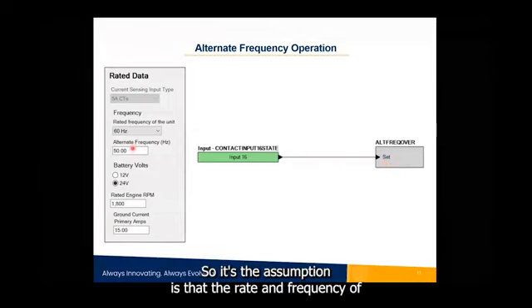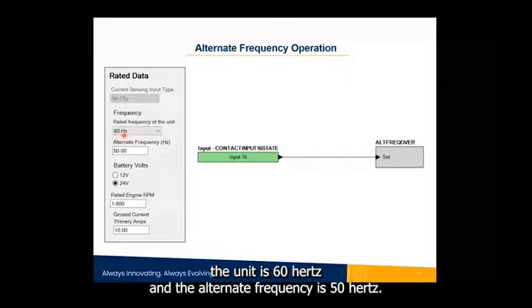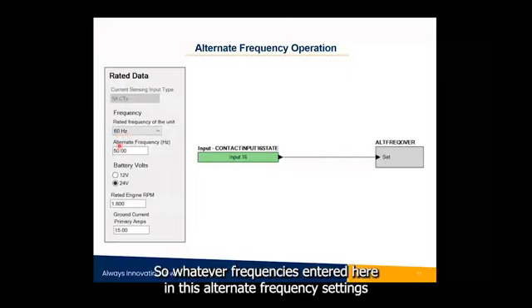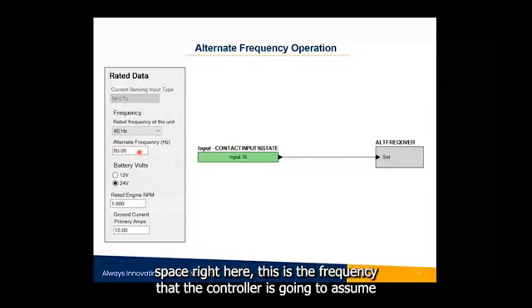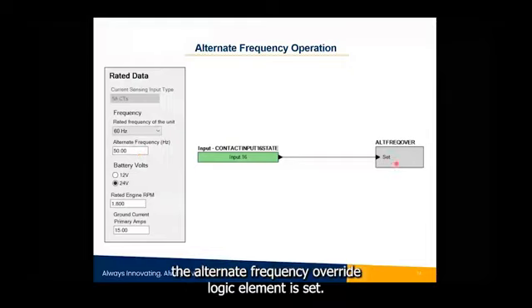So the assumption is that the rated frequency of the unit is 60 hertz and the alternate frequency is 50 hertz. Whatever frequency is entered here in this alternate frequency setting space is the frequency that the controller is going to assume once the alternate frequency override logic element is set. So we've talked about control. We also need to talk about protection.